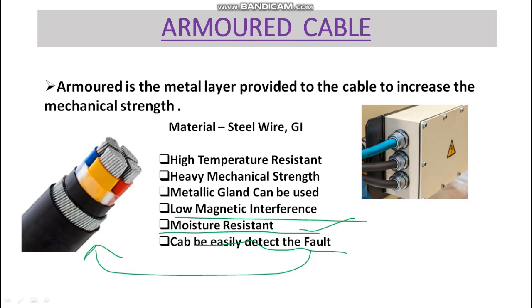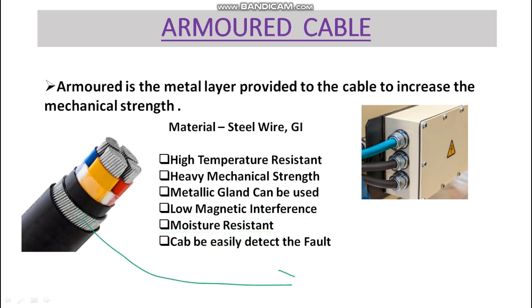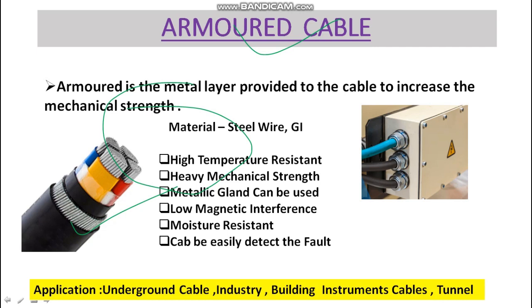Additional advantages include moisture resistance. Armored cable also allows easy fault detection — if a fault occurs, you can perform a continuity test with a multimeter between the armor and individual cores; continuity indicates cable damage, making faults easy to locate. Furthermore, the armor can also be used for earthing purposes.